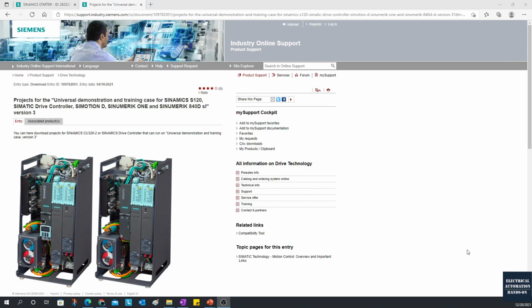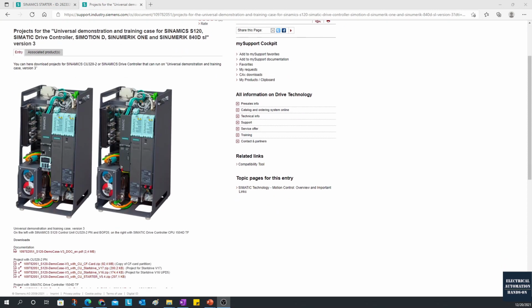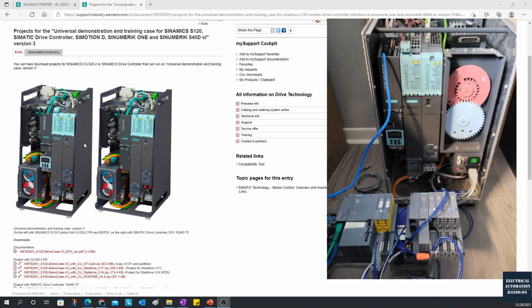And regarding the hardware I'm using, that's a SINAMICS S120, the typical Siemens demo site. Luckily, recently I got one demo site. This demo site has two servo motors. The servo controller is the SINAMICS CU320. This is the CU, this is the infeed module, and this is the motor module. This motor module can serve two servo motors, one blue, one red. The demo site I'm using is slightly older than the latest one, but the typical hardware style is similar. So this enables me to show how we can use the real hardware with the software to do this commissioning.